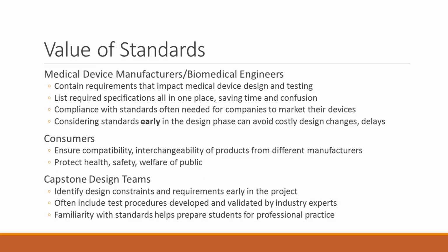So what is the value of standards? Why is it important for students to learn about it? Well, they benefit medical device manufacturers and biomedical engineers themselves, because they contain requirements that are needed that impact design and testing. They list the specs all in one place, which saves time and confusion trying to gather specifications and test procedures from different sources. And a lot of companies will not buy your product unless you comply with certain standards, so it's very helpful to the company that way.